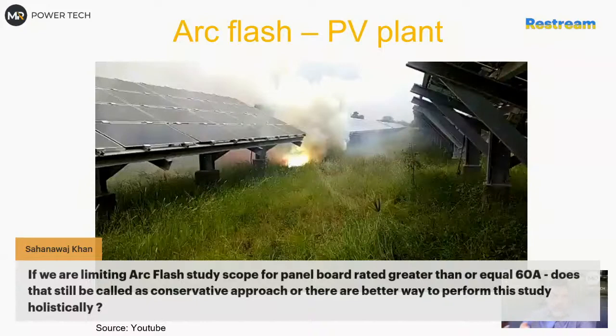So that's the point. If you just enter a random plant and you say, okay, where is your 208 volts, 2000 amp short circuit current panel list? So we know, okay, this panel is 2500, the other one is 10,000, this one is 1500 amp short circuit current rating expected. And usually you don't have it, it's like 99, or actually I'll call it 100%. You will never get this information. So you have to start somewhere.